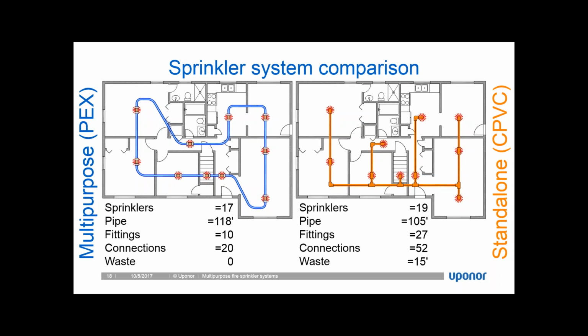Now it can be done in a loop configuration like I did with the Uponor PEX tubing, but that's not the way that it's typically installed. It just doesn't make sense from a cost standpoint to install a loop with CPVC piping. So for the drops on this, you'll see the sprinklers, you'll see the pipe, you'll see the fittings are way more than what is required on the PEX side, also the connections. The reason is when I get above each one of these sprinklers, because I've drilled a hole higher than where the sprinkler elevation is, I have to install a drop and then a special fitting, a special sprinkler adapter at the bottom of that drop.